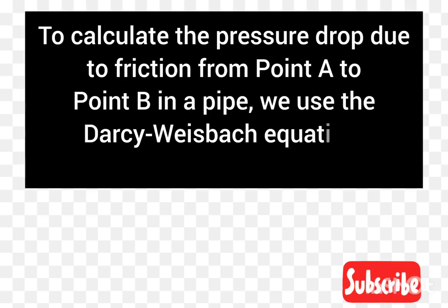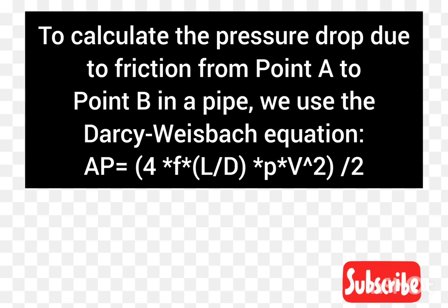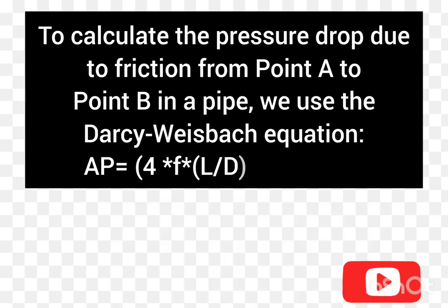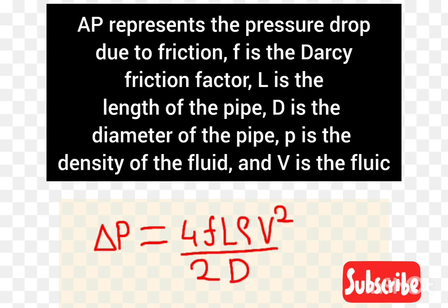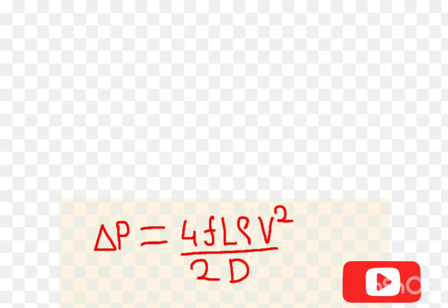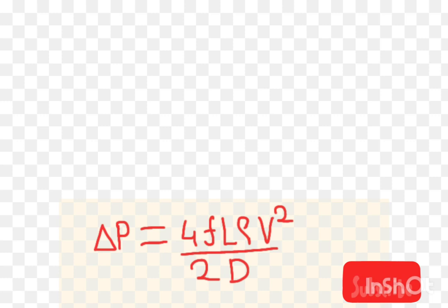To calculate the pressure drop due to friction from point A to point B in a pipe, we use the Darcy equation. The Darcy equation is: ΔP = 4 × f × L × ρ × V² / (2D), where ΔP is the pressure drop due to friction, f is the Darcy friction factor, L is the length of the pipe, D is the diameter of the pipe, ρ is the density of the fluid, and V is the fluid velocity.